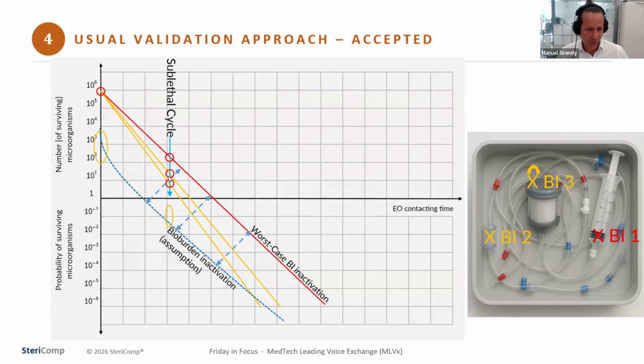Now the bioburden, in the sublethal cycle you would also do a test of sterility of this product, and you would see it's sterile or it's not sterile. So in this example here, it would most likely be sterile. There is a certain probability of growth, but let's say this is then sterile. And what is also interesting, this rate here that is important, and I will discuss in more detail in a minute, this rate here for the bioburden will now be not much worse than parallel to this worst case BI inactivation. Why? Because in the worst case, there are some highly resistant microorganisms like the Bacillus atrophaeus at this position, okay? All other positions will be less resistant, so you will have more or less a parallel curve, all right? And this is important, I'm going to tell you later.